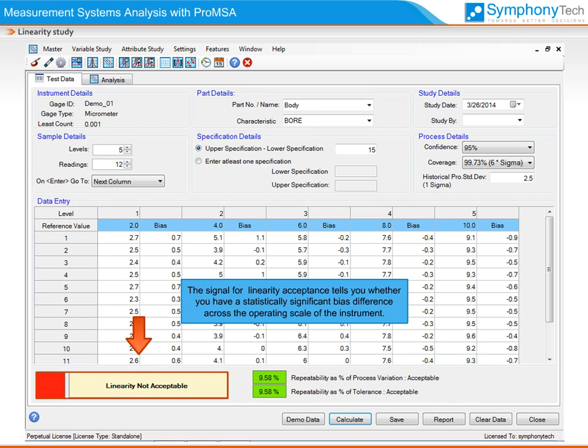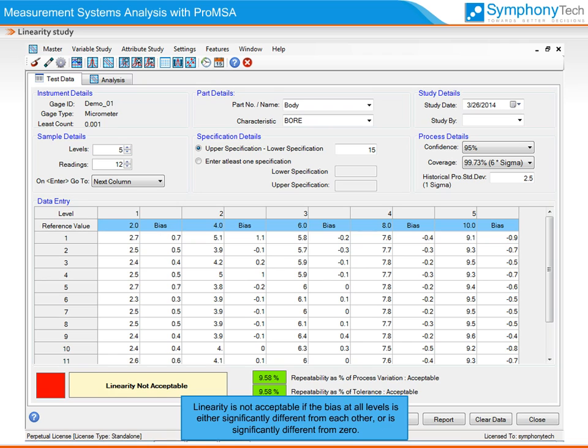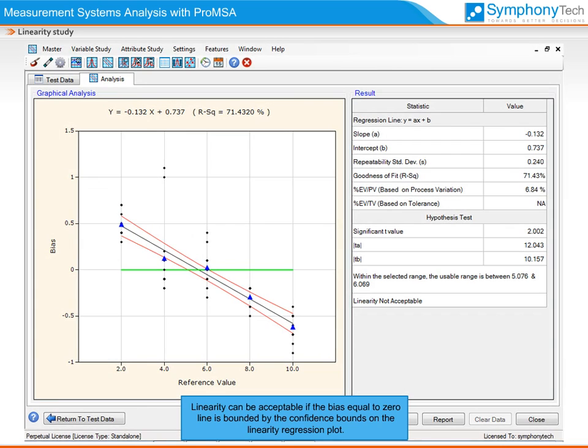The signal for linearity acceptance tells you whether you have a statistically significant bias difference across the operating scale of the instrument. This is established by performing a t-test on the data. Linearity is not acceptable if the bias at all levels is either significantly different from each other or significantly different from zero. For detailed analysis, look at the linearity plot on the next step. Linearity can be acceptable if the bias-equal-to-zero line is bounded completely by the confidence bounds on the linearity regression plot.